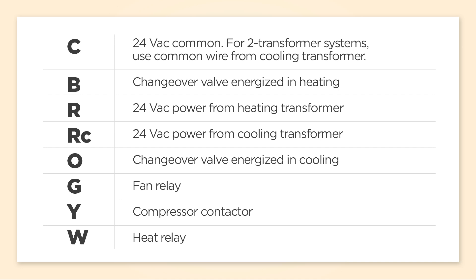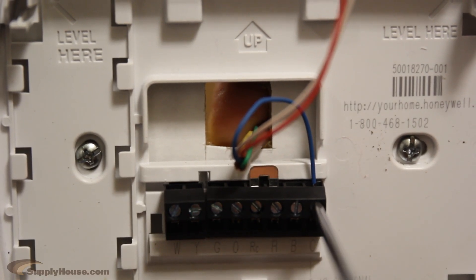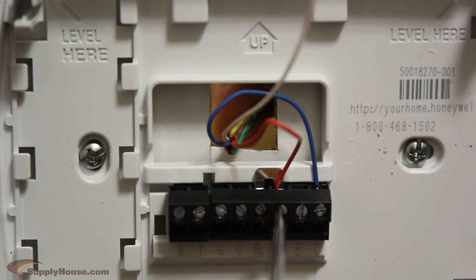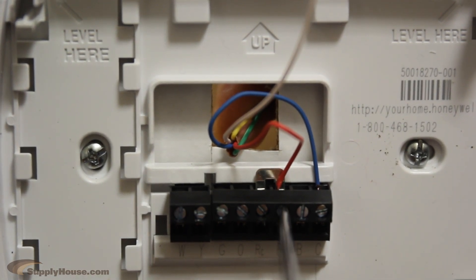With this installation, we used blue as a common. It is common throughout the system as it originates from the 24-volt transformer. The R is the 24-volt transformer's power. We wire that to the R of the STAT to provide control voltage. When used in conjunction with the C wire, it provides power for the STAT.